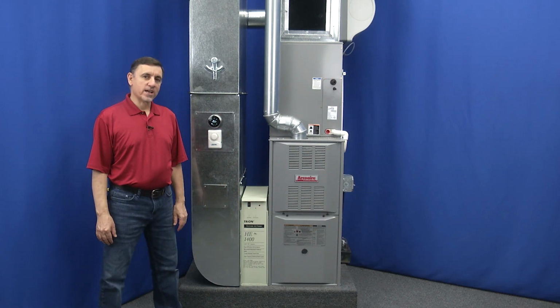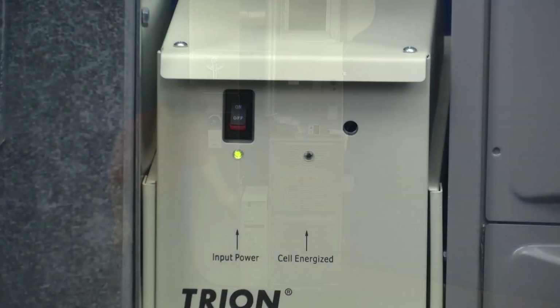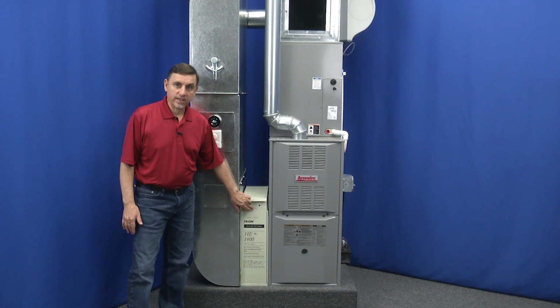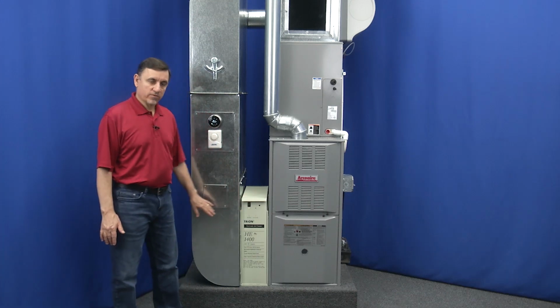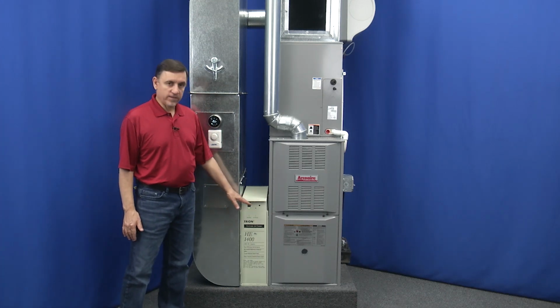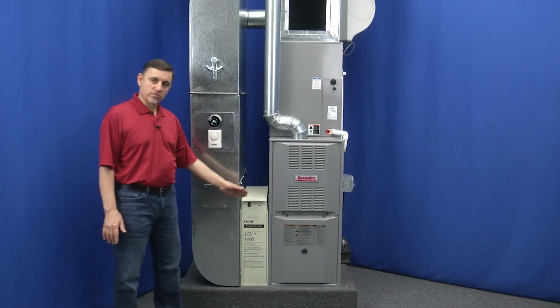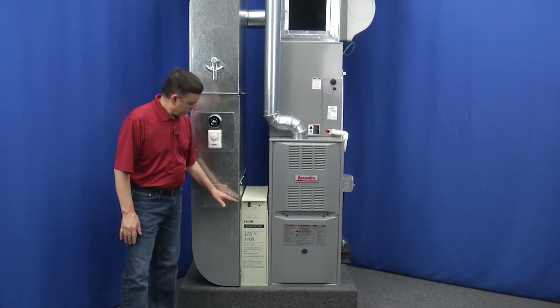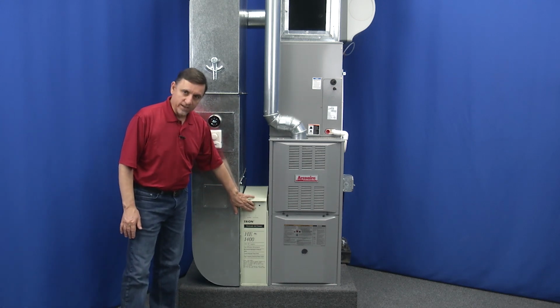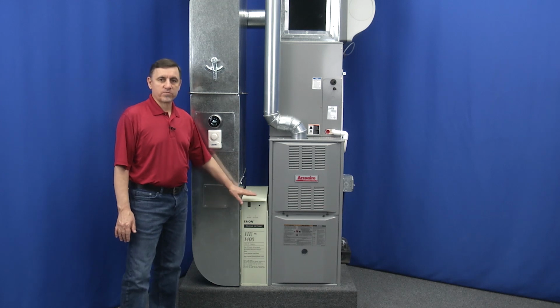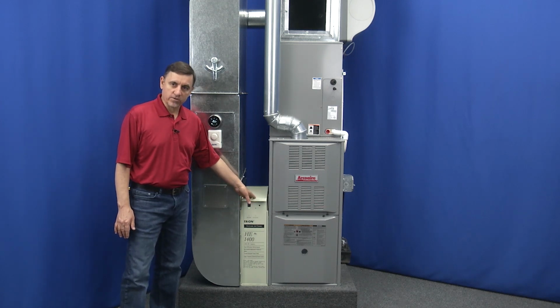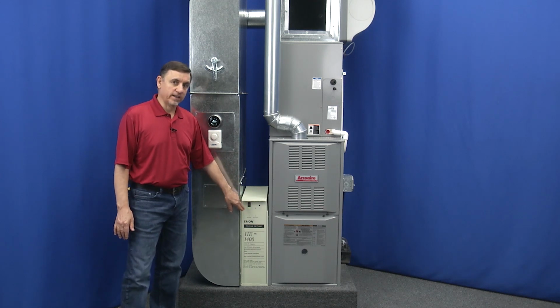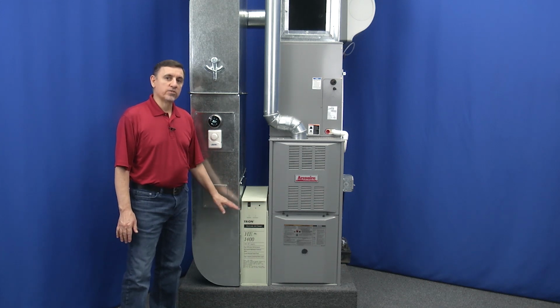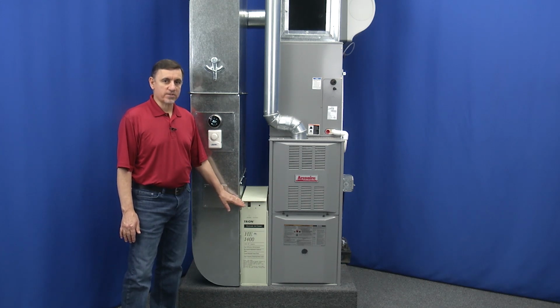Now we have our demo unit set up where the green light is lit, the red light is not, and the fan is on, so we're moving air through the unit. We have the airflow sensor calibrated, which I'll talk about later, and we have no red light. That means there's likely something going on inside either the power box or, more likely, the collector cells. So we're going to pull both collector cells out and do a quick test.